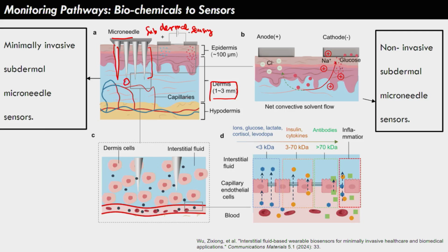So the tip diameter for good penetration, ideally, do you remember what it is? Very good. So it is around 20 microns or 20 micrometers. If it is around that, then the penetration is smooth and almost painless.